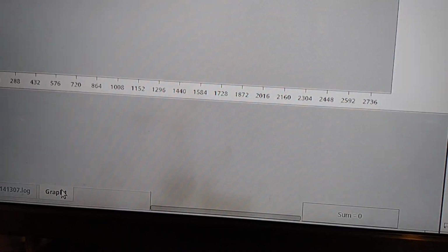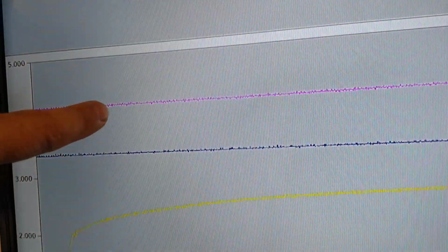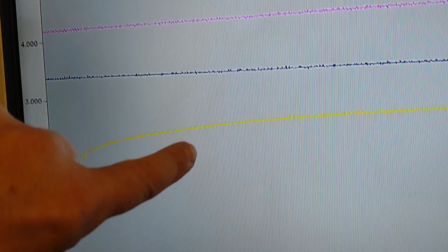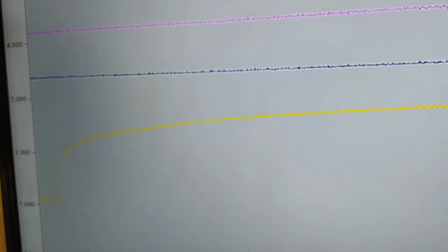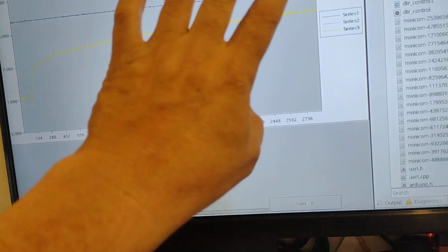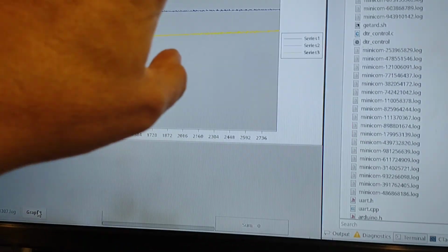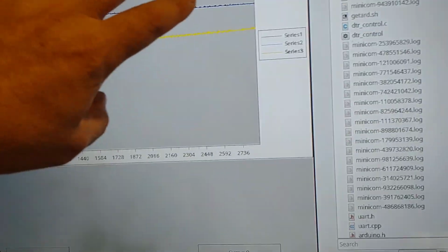I know that too. But you can see the underlying issue, and it's actually revealed in the graph, even though the values are wrong. It's still saying this one is not the same voltage as this one, and that's not the same voltage as this one. So the monitoring system is working in that sense. The calibration's wrong, but the system is working.